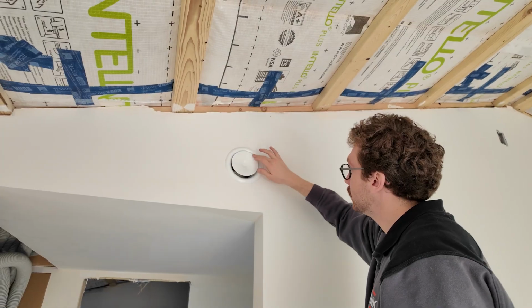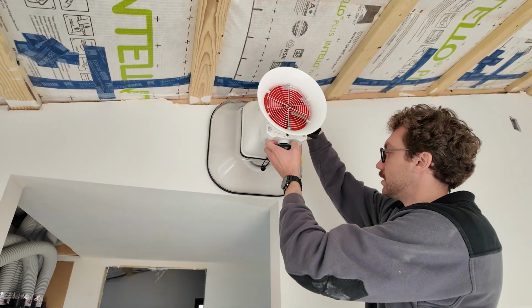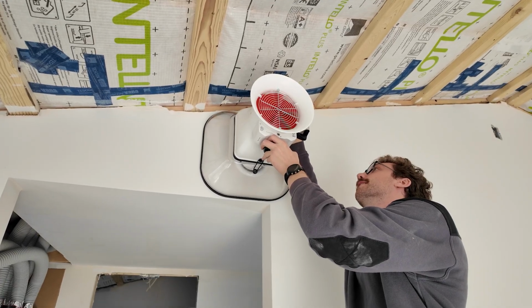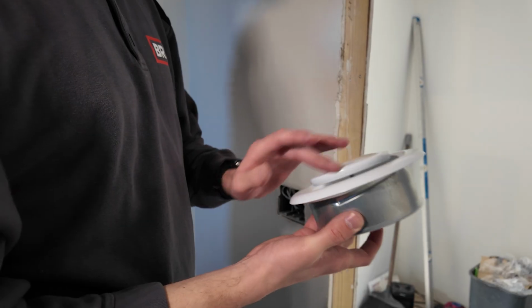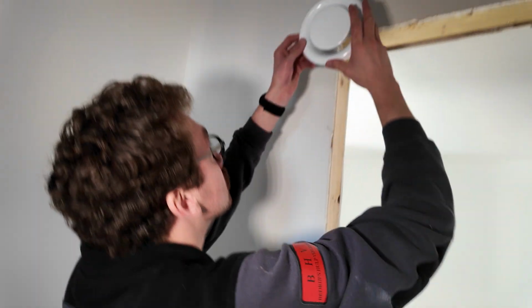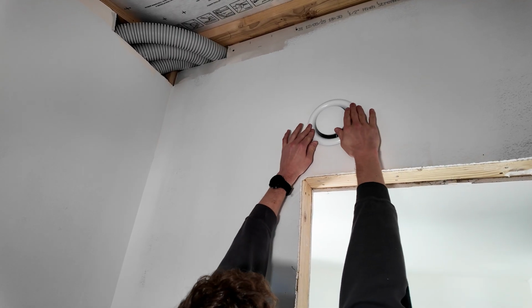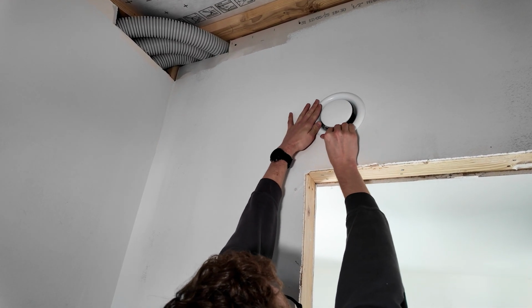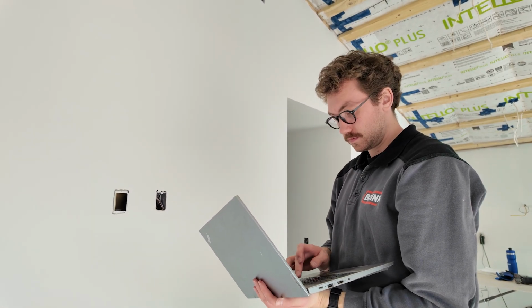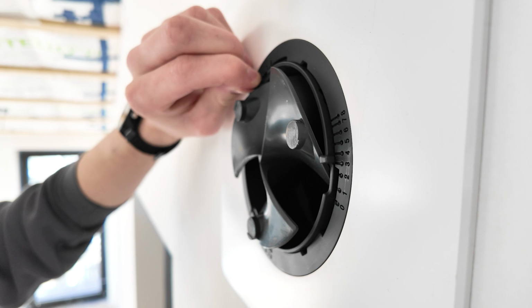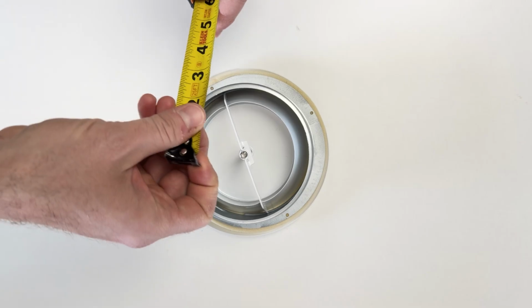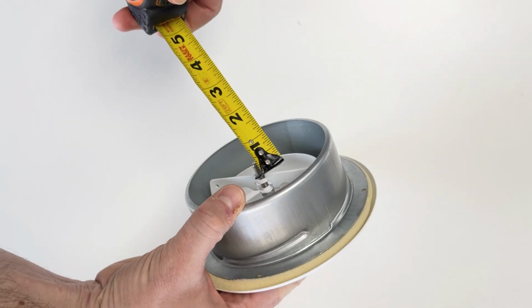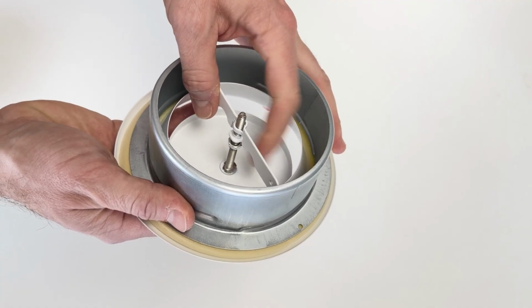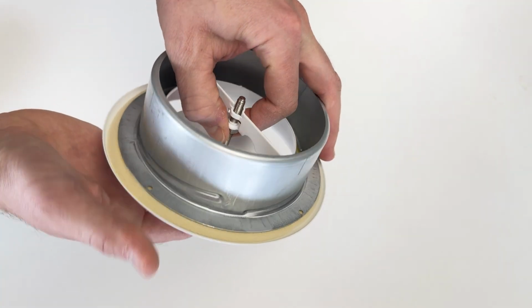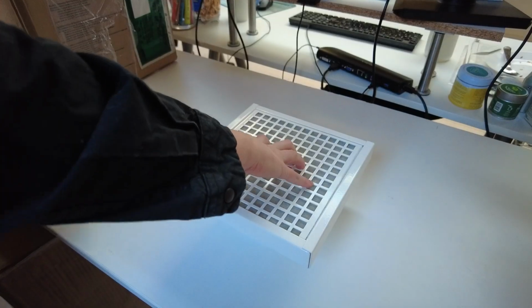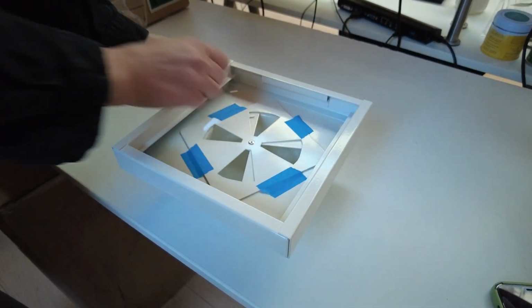Remeasure all the supply diffusers after each supply adjustment has been made to see the impact to the other locations. Remeasure all extract locations after each adjustment to the extract valves. We continue tightening and measuring until all rooms are at the designed flow rates. Be sure to record which diffusers were closed and by how much. For design diffusers, the setting can be recorded. For the round metal diffusers, the length of remaining screw thread should be measured. The lock nuts on the round metal diffusers should be tightened to secure the final settings. The kitchen diffuser's damper setting should be taped into place.